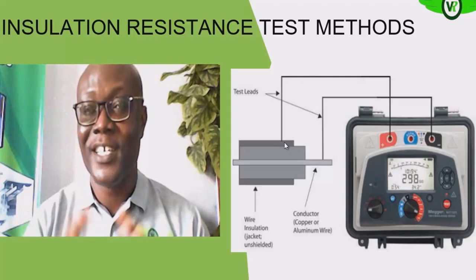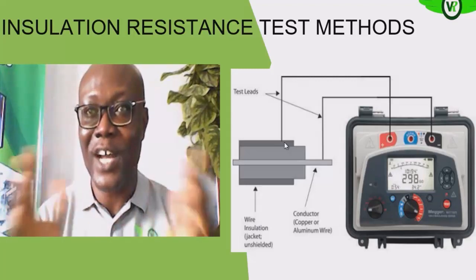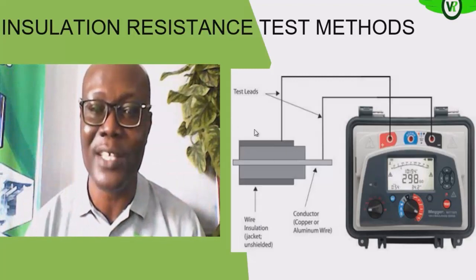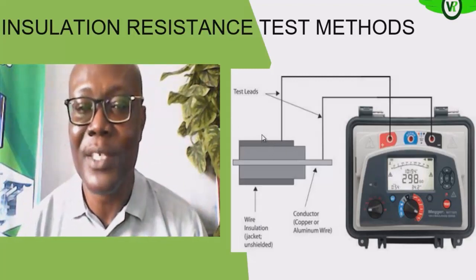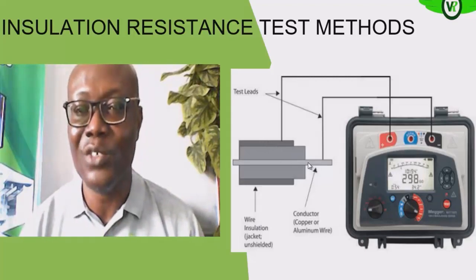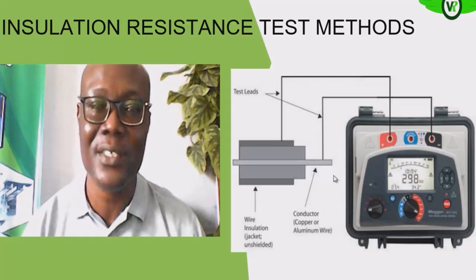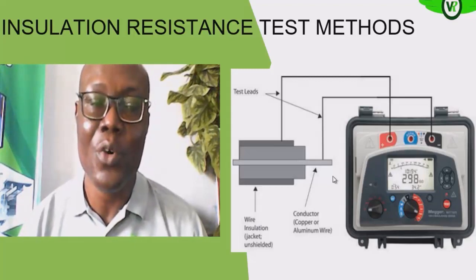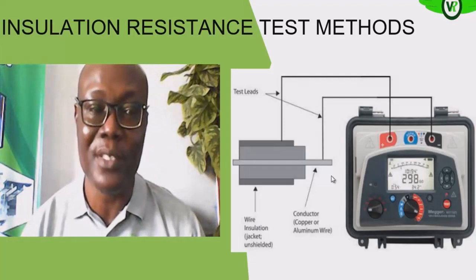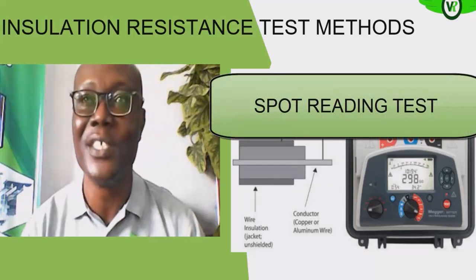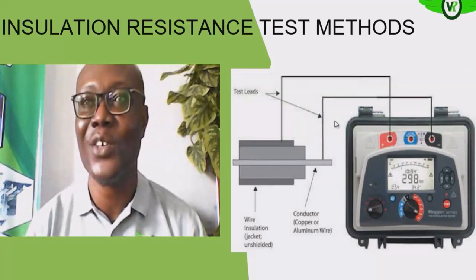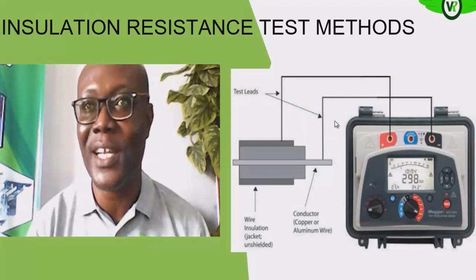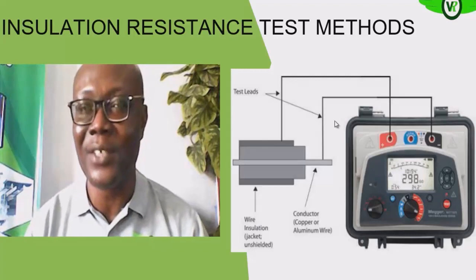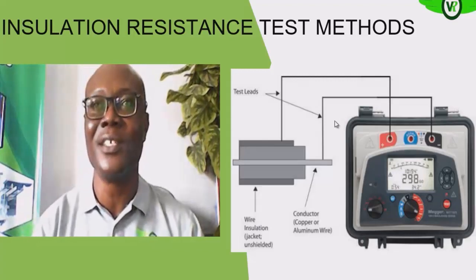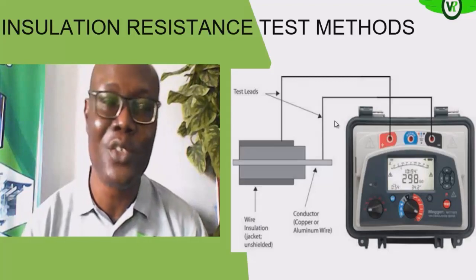that is the armoring cover, that rubber part around it, which is what you are seeing on the screen now. So you can place it there, between there and the conductor, and then you inject and get your resistance reading. So what we have just described is the spot reading test. That is, you inject and take a single reading from your equipment, either between line to line, line and ground, phase to ground or phase to phase, on your equipment. So you take just one reading.